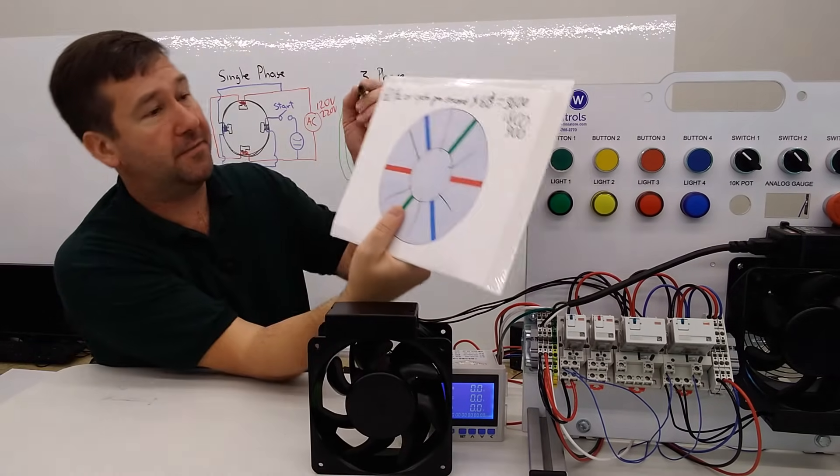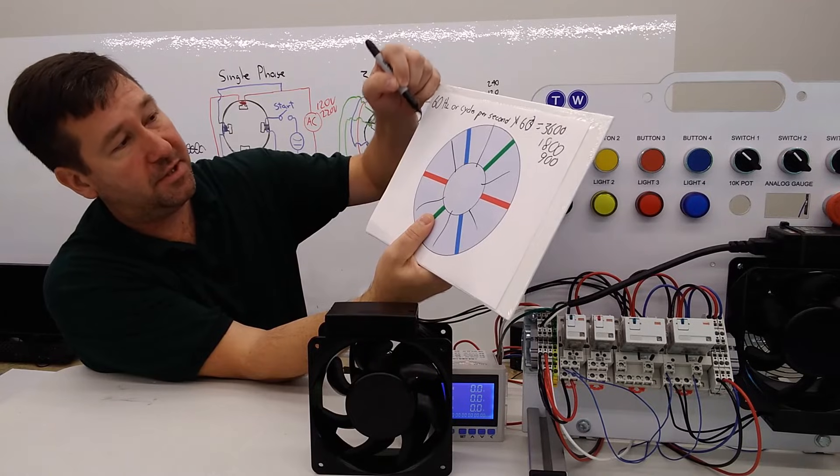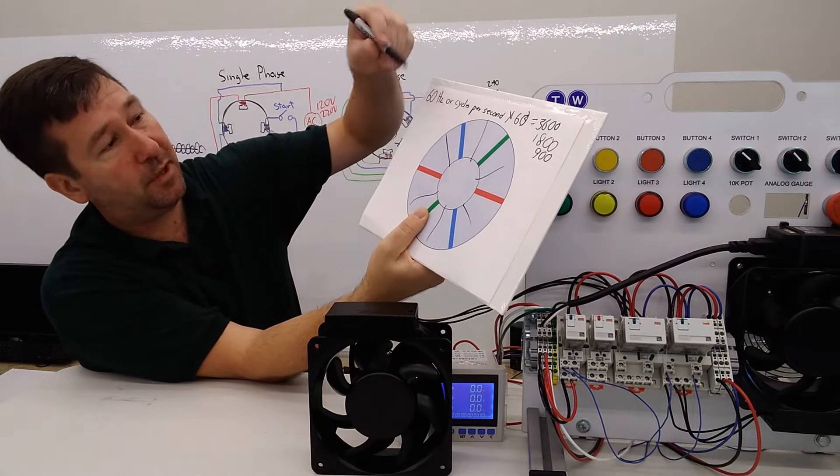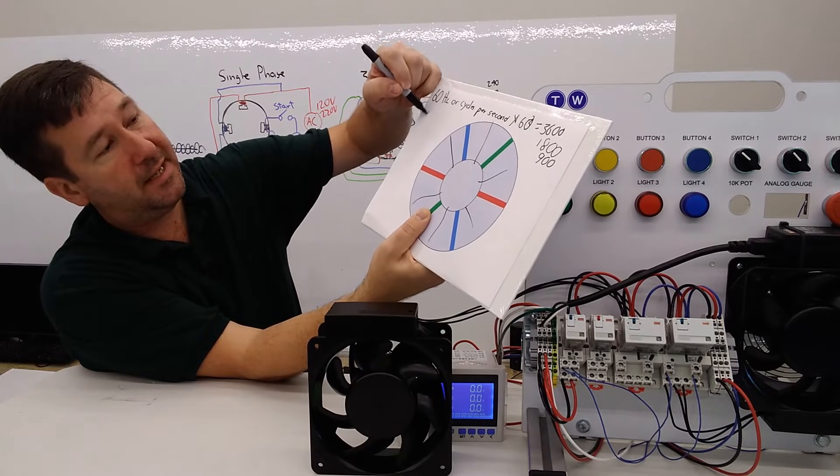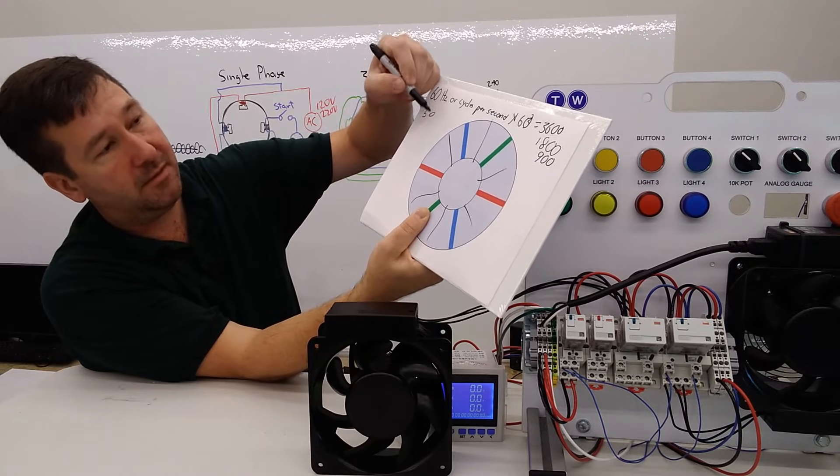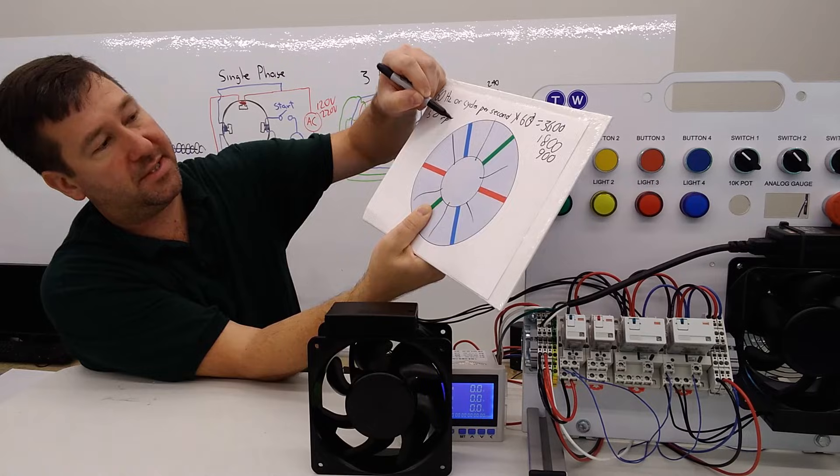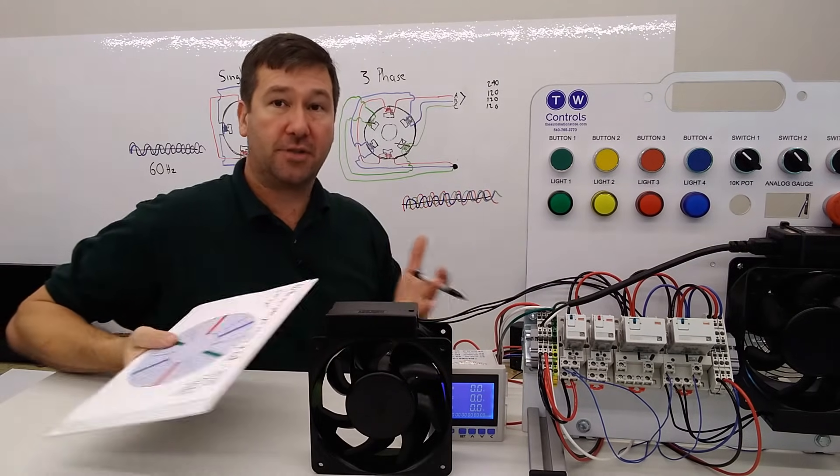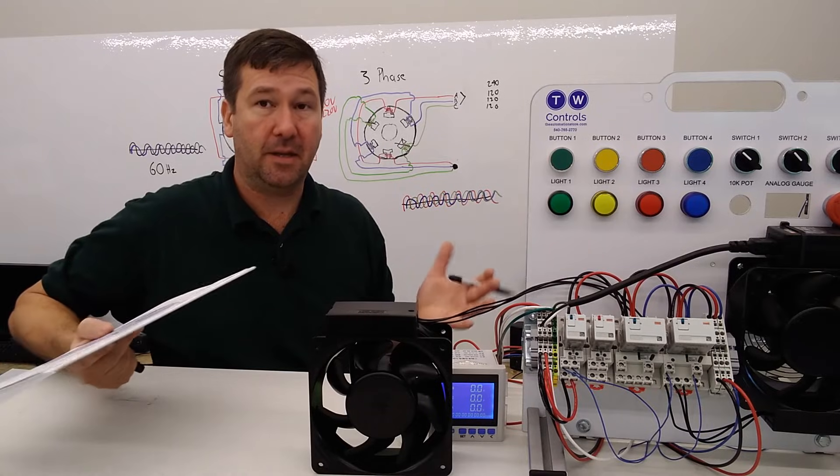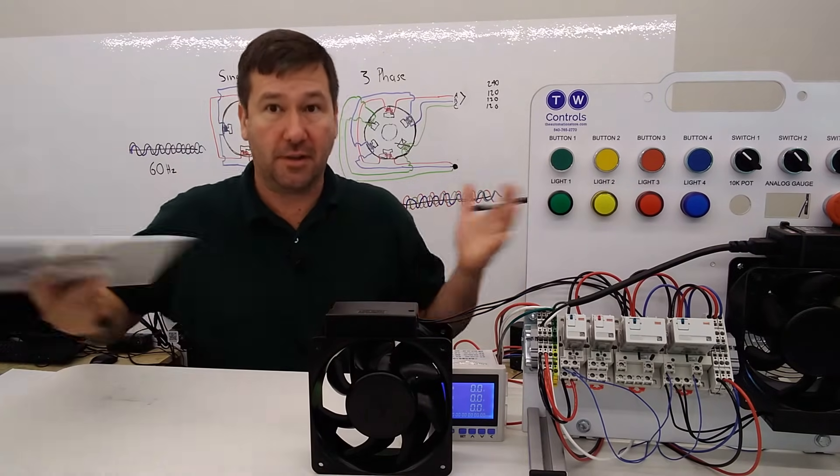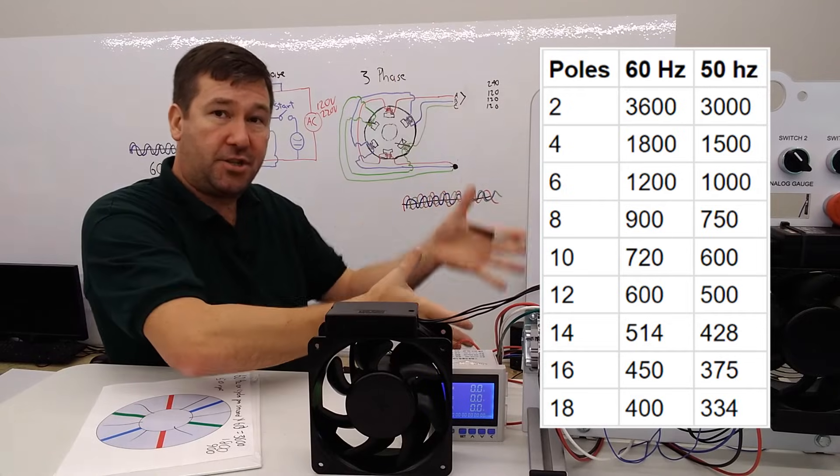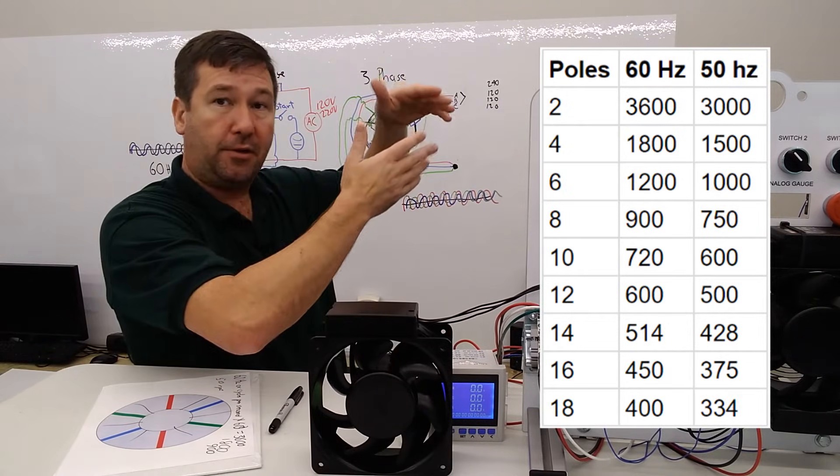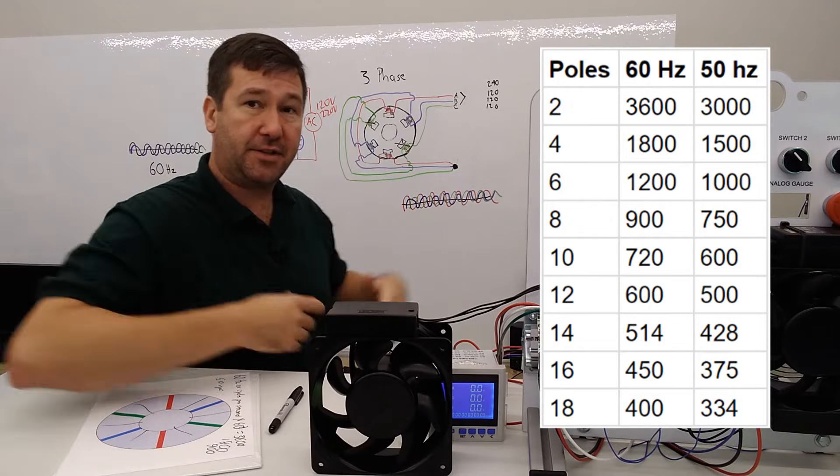Also, for the people in the 50 hertz world, all you would do is change this 60 to a 50. If we had a two-pole motor, then it would be going 50 revolutions per second, and that means that a 50 hertz two-pole motor is going to run 3,000 RPM, whereas a 60 hertz two-pole motor is going to run 3,600. Here's a really nice chart showing the RPM based on the number of poles and whether you have 50 or 60 hertz.